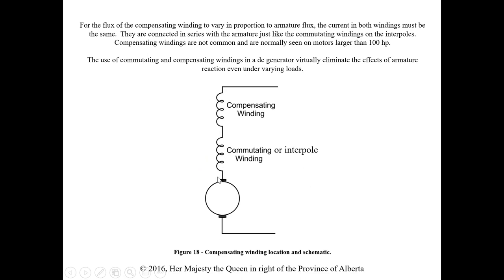Both commutating and compensating windings are shown hooked in series so they see the same current to cancel out the armature reaction effects. They are wound completely opposite to the armature winding to oppose that magnetic field. Compensating windings are not common and are normally seen only on motors larger than 100 horsepower. The use of commutating and compensating windings virtually eliminates the effects of armature reaction even under varying loads, maintaining that main field flux as straight as possible to eliminate arcing and sparking on the brushes.